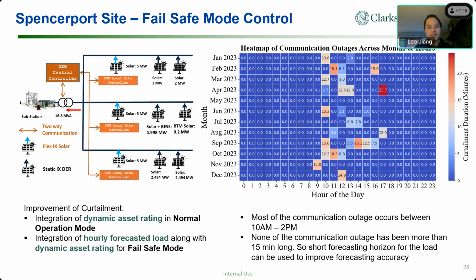For the Spencerport PV site, we did some study there. To improve curtailment, we could integrate the dynamic asset rating in the normal operation mode. Indeed, we can also integrate the dynamic asset ratings in the fail-safe mode. As I said, the local controller and the central controller communicate with each other very frequently. And on top of the dynamic asset rating, you can also use the hourly forecasted load to update the dynamic hosting capacity for the fail-safe mode curtailment.